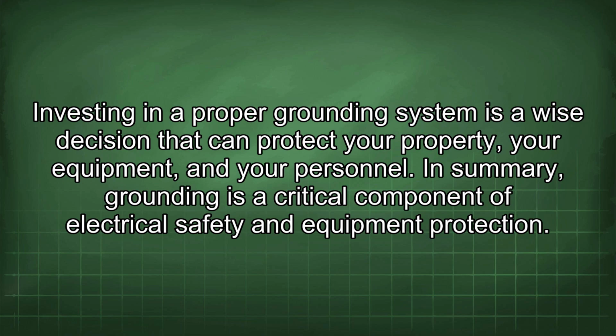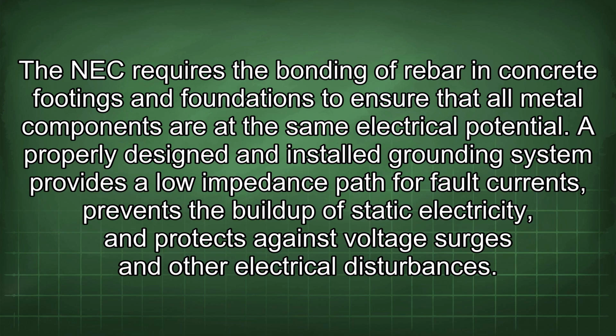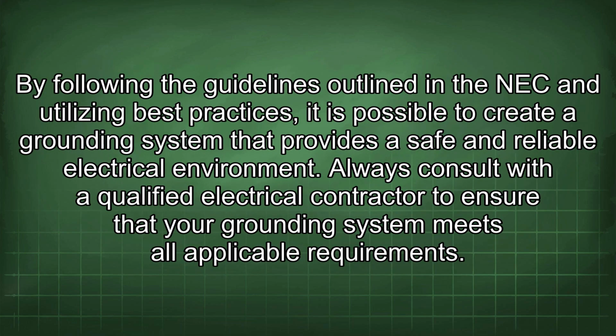In summary, grounding is a critical component of electrical safety and equipment protection. The NEC requires the bonding of rebar in concrete footings and foundations to ensure that all metal components are at the same electrical potential. A properly designed and installed grounding system provides a low impedance path for fault currents, prevents the build-up of static electricity, and protects against voltage surges and other electrical disturbances. By following the guidelines outlined in the NEC and utilizing best practices, it is possible to create a grounding system that provides a safe and reliable electrical environment. Always consult with a qualified electrical contractor to ensure that your grounding system meets all applicable requirements.